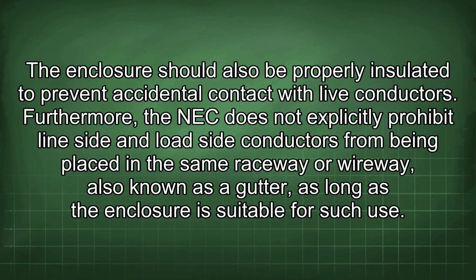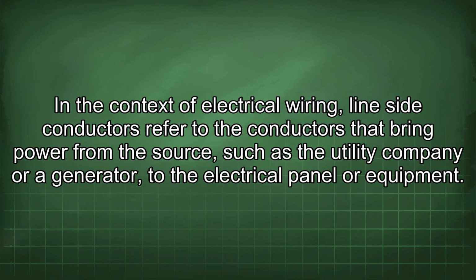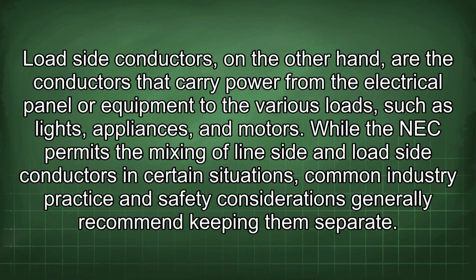Furthermore, the NEC does not explicitly prohibit line-side and load-side conductors from being placed in the same raceway or wireway, also known as a gutter, as long as the enclosure is suitable for such use. In the context of electrical wiring, line-side conductors refer to the conductors that bring power from the source, such as the utility company or generator, to the electrical panel or equipment. Load-side conductors, on the other hand, are the conductors that carry power from the electrical panel or equipment to the various loads, such as lights, appliances, and motors.